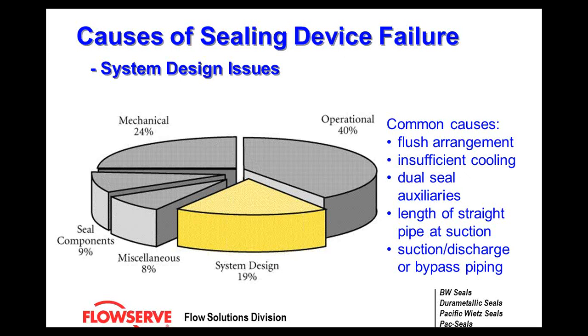The length of straight pipe at suction: on some older skid-mounted pump systems, designers put a 90-degree elbow right at the suction. This causes a turbulent region just before flow goes into the impeller eye — eddies, like those you see in a stream, create instabilities in the rotating assembly, again a cause of seal failure. All the suction, discharge, and bypass piping associated with your system, if not engineered correctly or if changes were made over the years without being accounted for, can cause real headaches.